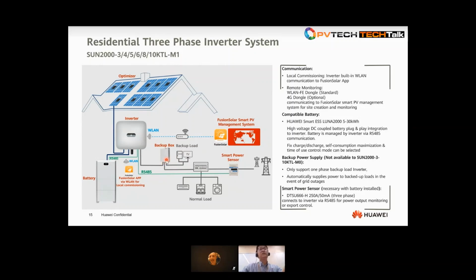One thing I want to emphasize is that the power we get from the three-phase backup box is still single-phase. The inverter, say, is a 10 kilowatt three-phase inverter, but we can only connect one phase to the backup box. So of the 10 kilowatts, one phase only gives 3.3 kilowatts. So it's single-phase power here, and this needs attention.